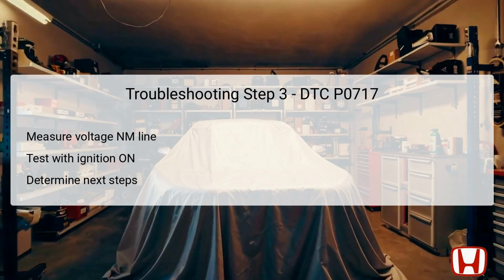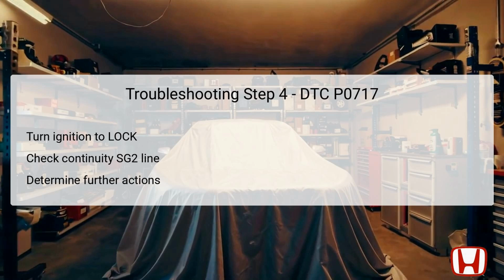If this voltage measurement is positive, it confirms that the circuit is functioning properly, and you will proceed to the next troubleshooting step. If you do not get the expected voltage in this instance, it indicates that there is likely an issue within the NM wire leading back to the PCM, which will necessitate further inspection to locate and repair the fault. The fourth troubleshooting step focuses on checking for continuity in the SG2 line.